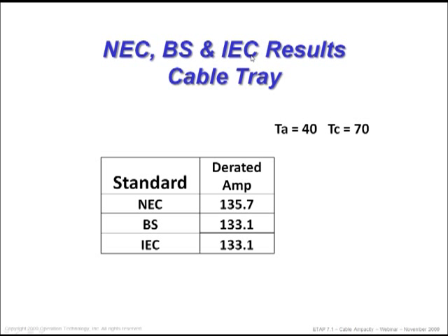For this cable tray comparison, we've set the ambient at 40°C and the conductor temperature at 70°C — limited because of splicing, termination, or similar constraints. The ampacity across all three methods comes out very close to each other. In this particular case, BS and IEC give identical results, while NEC gives you a little bit more current.